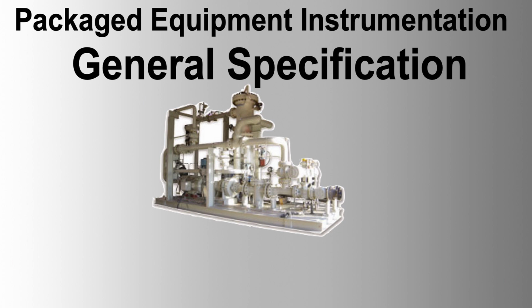Pressure transmitters should consist of a diaphragm or bellows with a capacitance capsule or electrical strain resonance frequency transducer unit equipped with local digital indication. Transmitters should have non-interacting zero and span adjustment and integral 3-valve manifolds, certified for the electrical area classification.